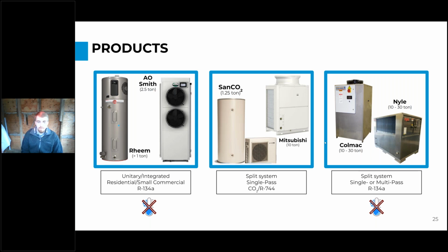And then we have the split system single pass heat pumps. I have CO2 separated out here just because with CO2 split system heat pumps, you're usually just going to put the heat pump itself located outdoors, and then you're going to plumb the hot water into a large storage tank.